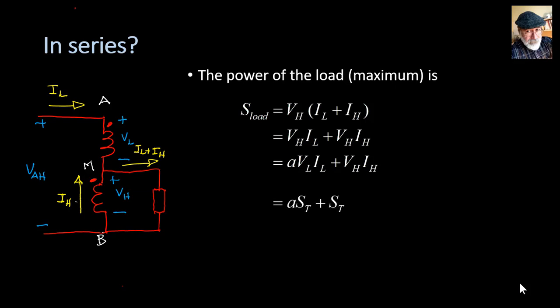We can simplify, factor out, and write it this way. A, the ratio, is VH divided by VL. In the end, we say that the maximum power that we can feed with this arrangement is greater than the rated power of the transformer itself. What is the coefficient? VH plus VL divided by VL, rated values.